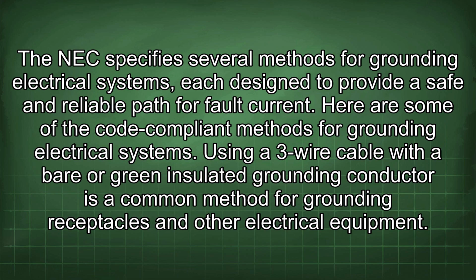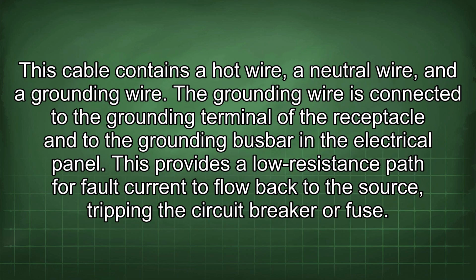Using a 3-wire cable with a bare or green insulated grounding conductor is a common method for grounding receptacles and other electrical equipment. This cable contains a hot wire, a neutral wire, and a grounding wire. The grounding wire is connected to the grounding terminal of a receptacle and to the grounding busbar in the electrical panel. This provides a low resistance path for fault current to flow back to the source, tripping the circuit breaker or fuse.